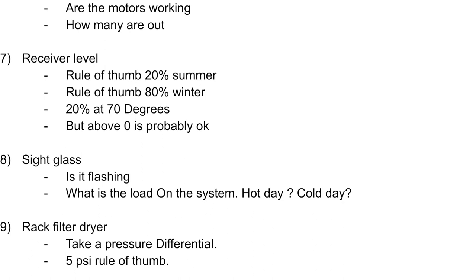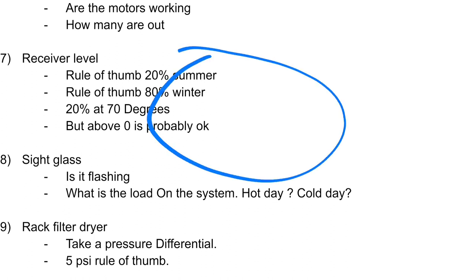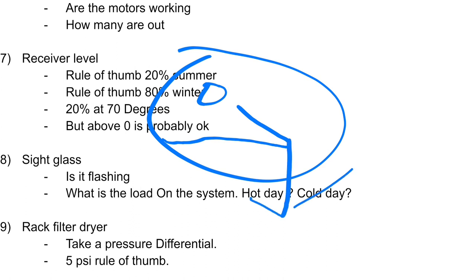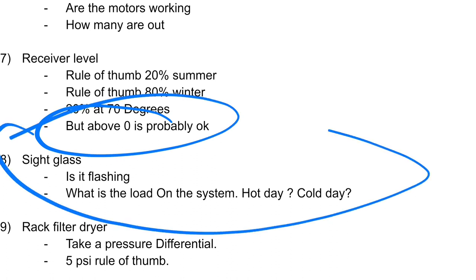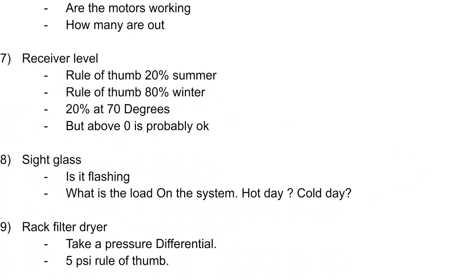We service a lot of stores that like to run the receiver level basically at zero. Even in all honesty, if you look at the receiver gauge, you have a zero right there. The needle is literally just below zero, but it's not straight down. That's how they like to run it, just as close to nothing as possible, and the systems work fine. So basically, as long as you're not at absolutely zero and your sight glass is clear, you don't have low refrigerant.